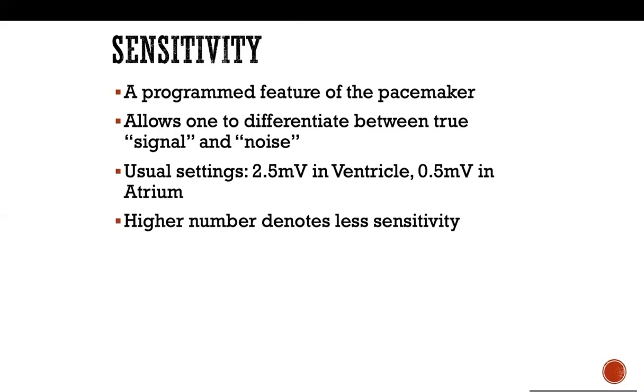So if, let us say, the QRS measurement is 5, and we program the device to see anything above 2, that means most likely it's going to see every single ventricular signal. So we aim for sensitivity to be about 50% of the R wave. For example, if the R wave is 10, a sensitivity of 5 is actually good. If you want it to be more sensitive, you might lower the number. That means you'll see anything that is above 2, or you could see anything that is above 1, which will be even more sensitive.